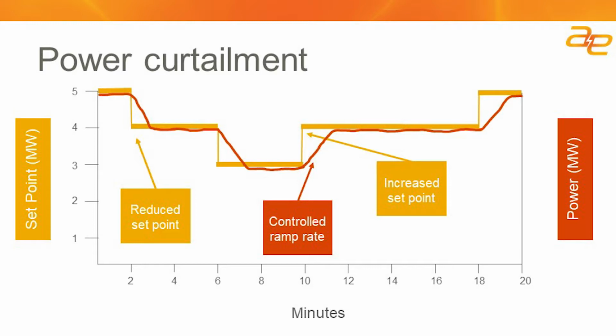When we change the plant set point from 5 to 4, what we actually do is send an updated command to the inverters to not run at 100% output, but to run some level below that, maybe 80% output. And it'll actually be perhaps a little higher than 80%, so that we can compensate for losses, or if a cloud comes, we can turn up the inverters that are generating to compensate for that and do closed loop control. Or we can do open loop control, knowing how many inverters we have and what the target is, and command the inverters that are available so that we get the desired output, whether it's 5 megawatts, 4 megawatts, 3 megawatts, or any point in between.